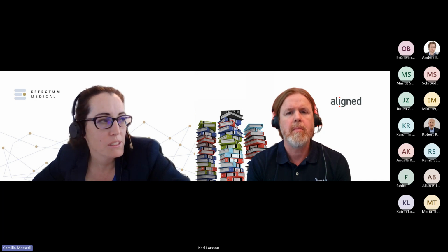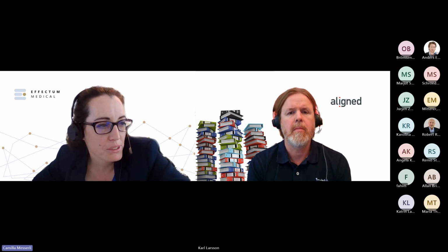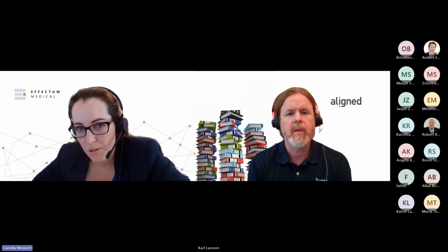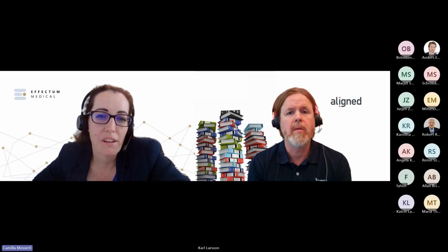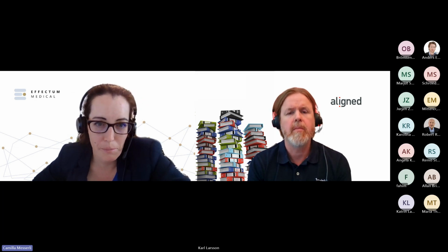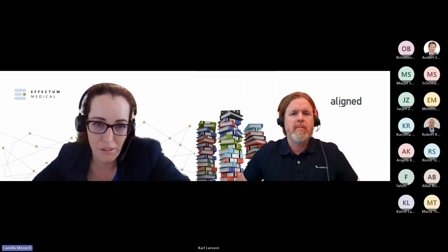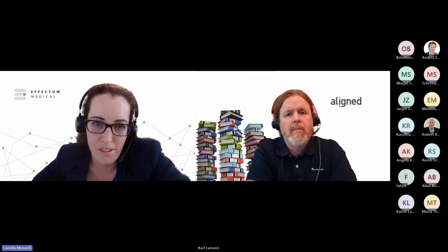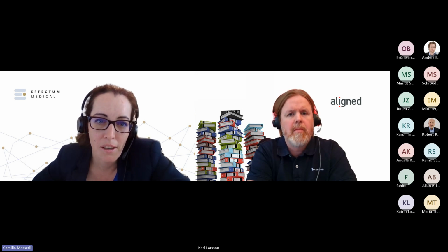And the other thing is a few issues that I've seen in the past, that they, for example, just state that a literature update has to be made, but not how. And then you already have an audit finding. Depending on the auditor, but we all know that there can be nice auditors and picky auditors. If you get the picky one, he will say, oh, you have to write the actual literature search protocol method, the keywords, somewhere. And that's where we just say, hey, just reference the literature search protocol from your V&V. You make sure that's kept up to date and so on. So those are a few of the official things that are quickly forgotten.